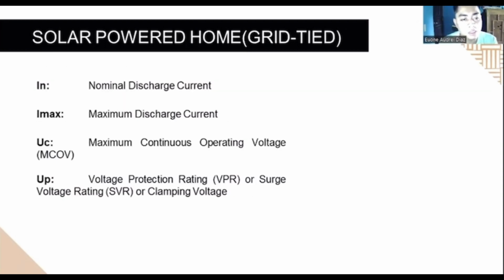Ang meaning daw po ng IN is the nominal discharge current. Sa IMAX, maximum discharge current. UC or MCO, sa UC na is maximum continuous operating voltage or the MCOV. Yun yung meaning kanina ng UC. And the UP is the voltage protection rating or VPR or surge voltage rating, SVR or clamping voltage.